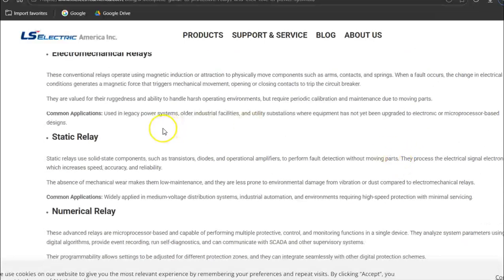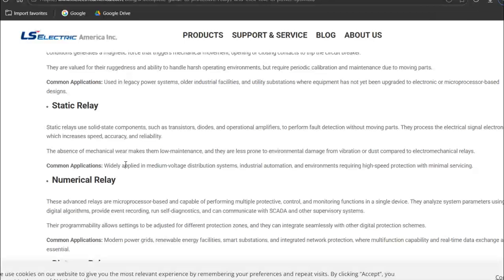Older electromechanical ones, they use magnetic induction, and they'll spin a wheel, and if the wheel spins long enough, it hits a current trip device, the contacts close, and its output will send a trip signal. Static relays, they're another name for solid state relays. Electronic, no physical mechanical parts, no springs. They are just a little easier. No moving parts means less maintenance, less prone to environmental damage from vibration or dust or dirt. Solid state stuff is pretty durable.